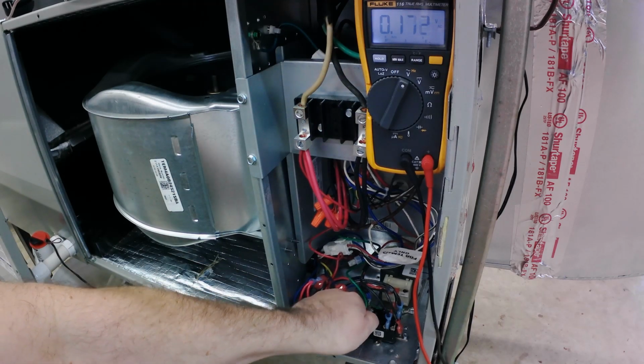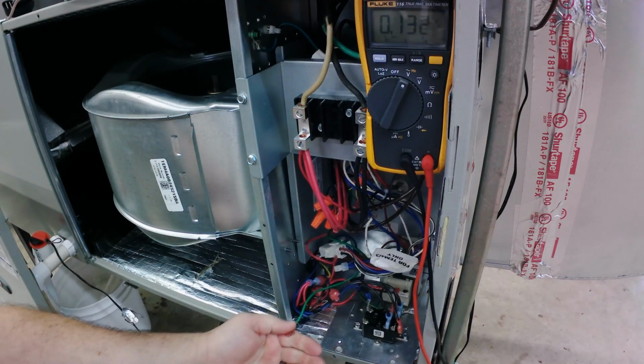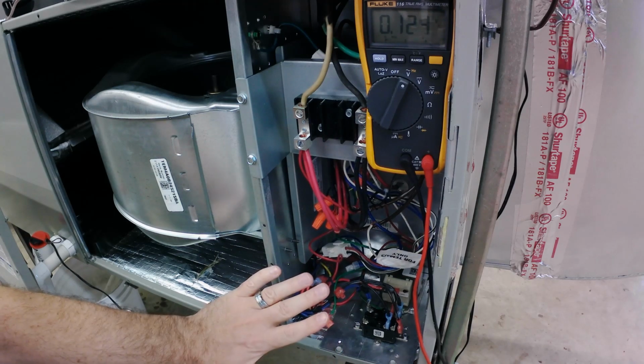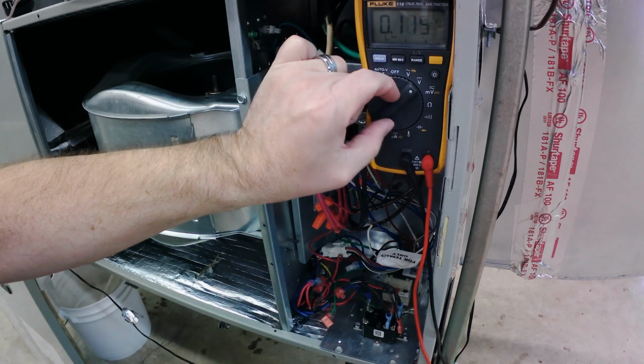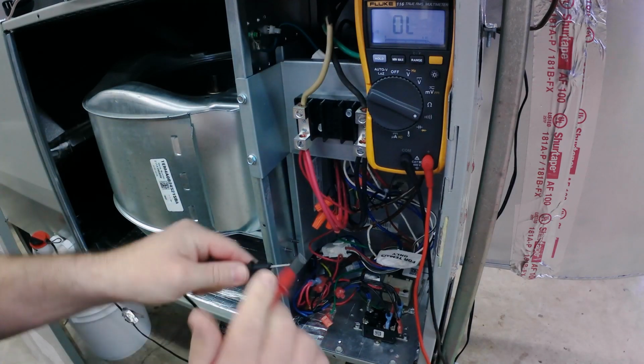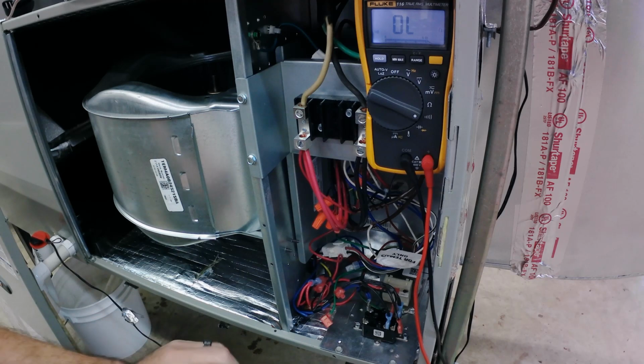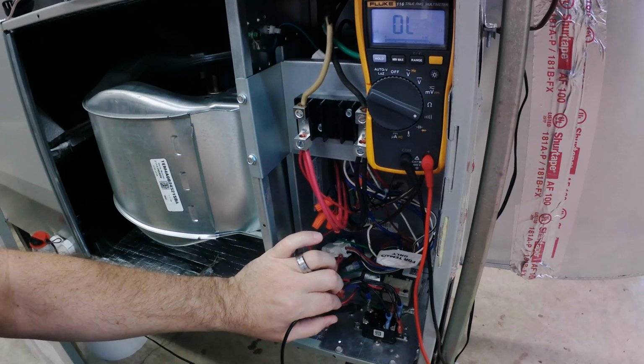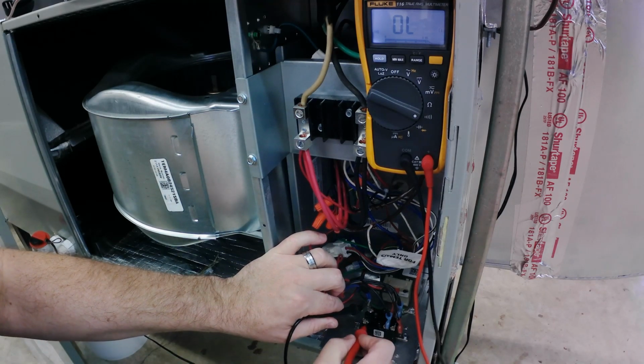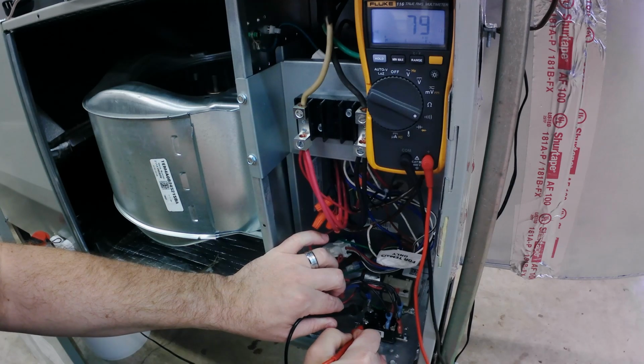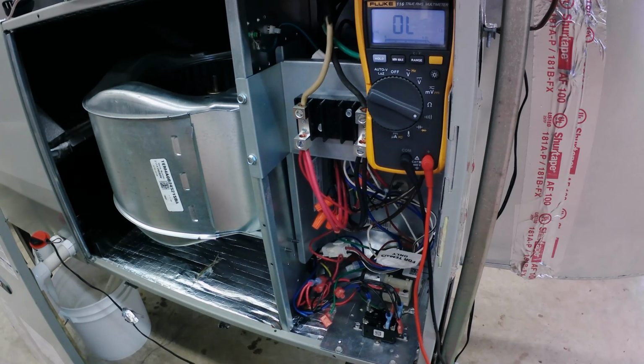I would leave everything powered on, and this is me. I'm going to take the green off, okay? So no 24 hot. And what I'm going to do is ohm out, or use continuity rather. Either one, they're both related. And just because you have 24 volts going to the coil terminals doesn't mean you got a good coil. You could have an open coil and that 24 volts is not going to do anything.